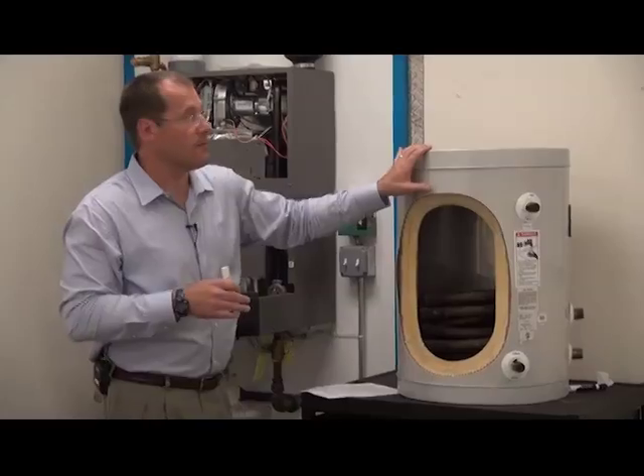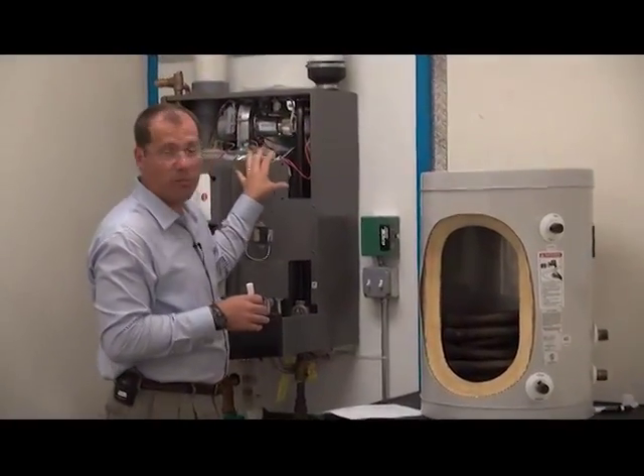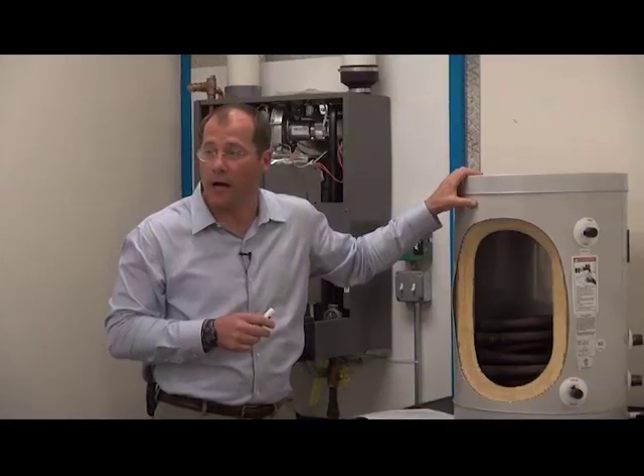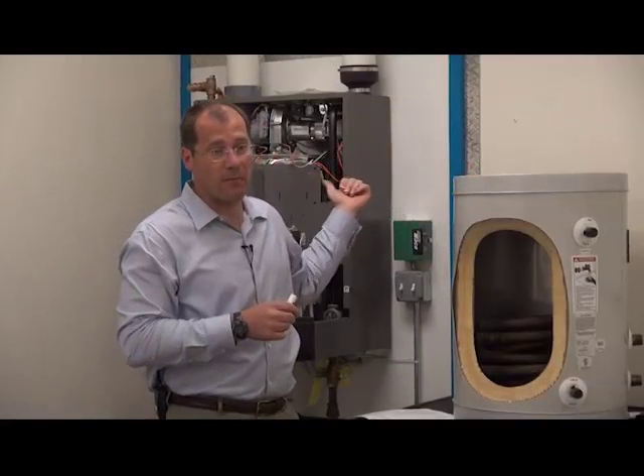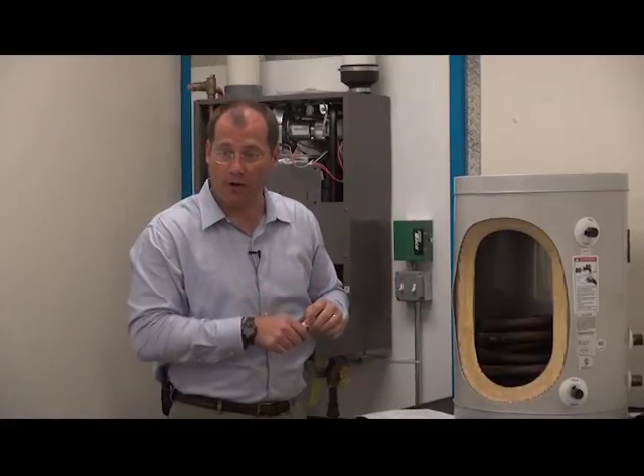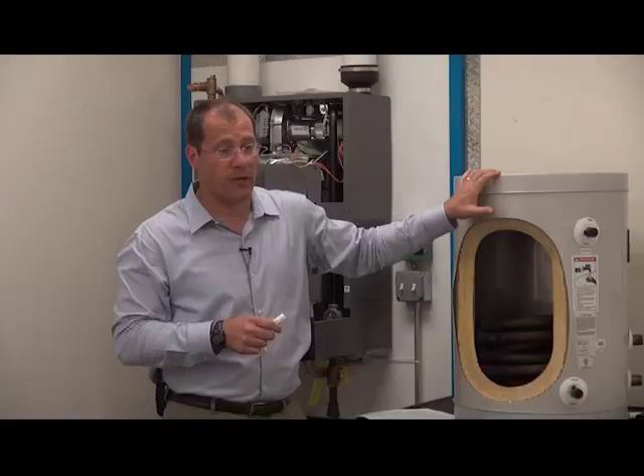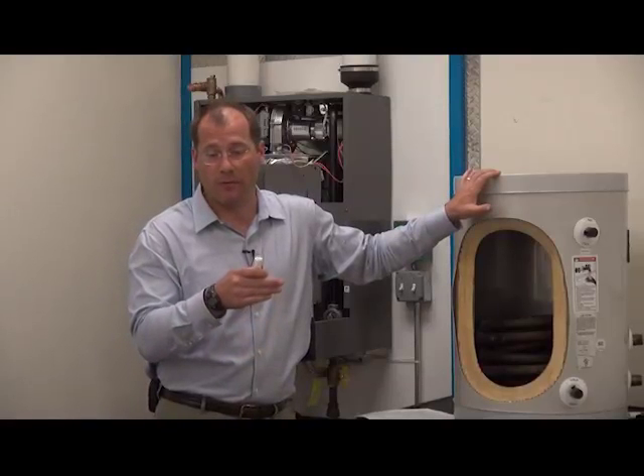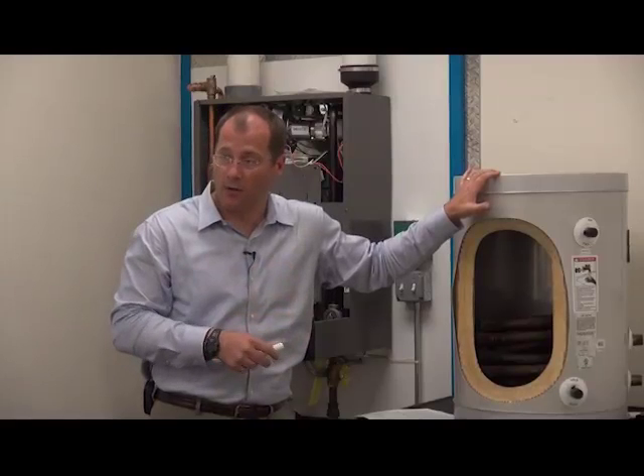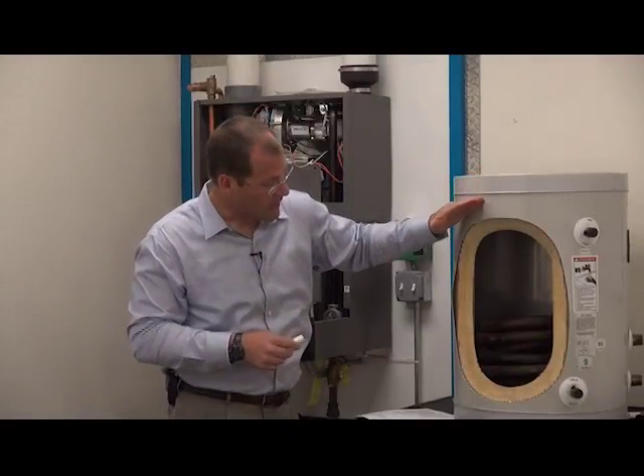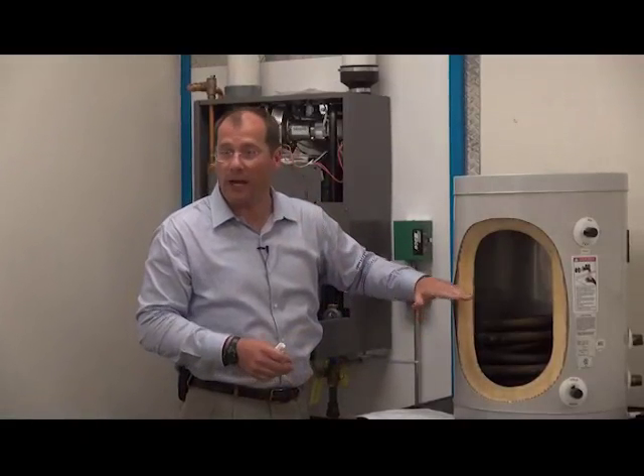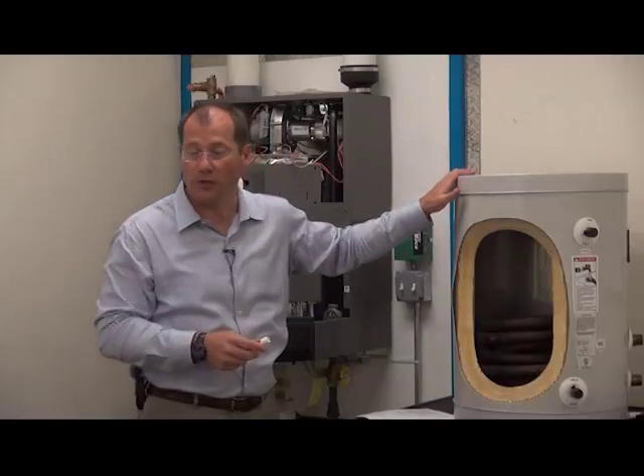One of the rules of thumb is the smaller the boiler, the larger the storage on the hot water heater needs to be because it doesn't have the horsepower or the BTUs to rapidly recover that water. So what we do is we ask about if we determine their shower use, we can calculate how many gallons a minute they need on a typical day, and we make sure that they can draw down this tank and meet those needs, and then the boiler is working to bring it back up over 15, 20 minutes.